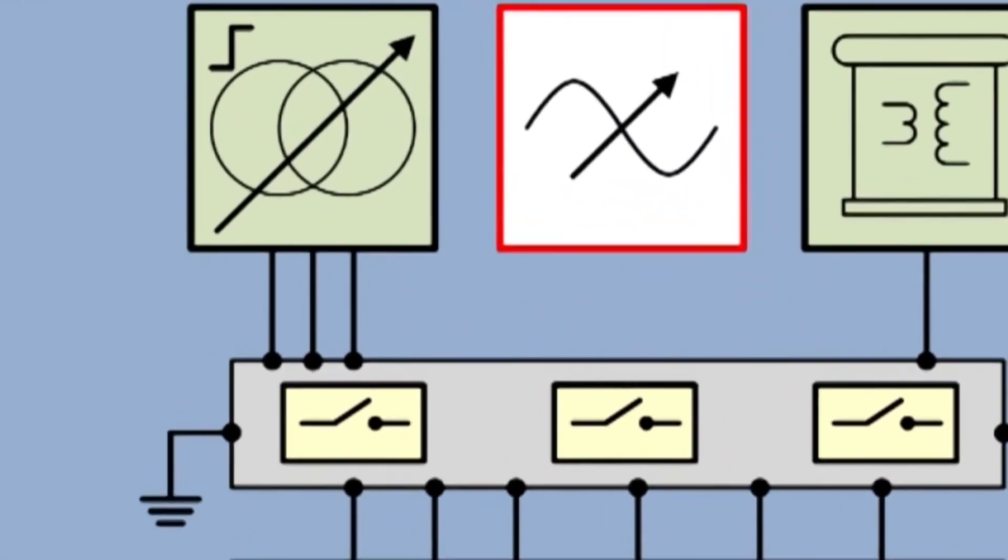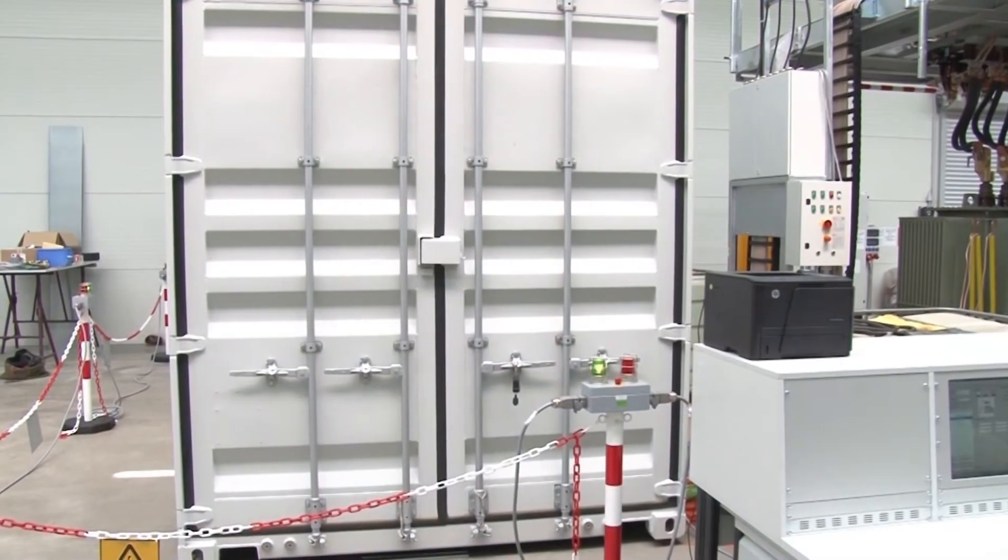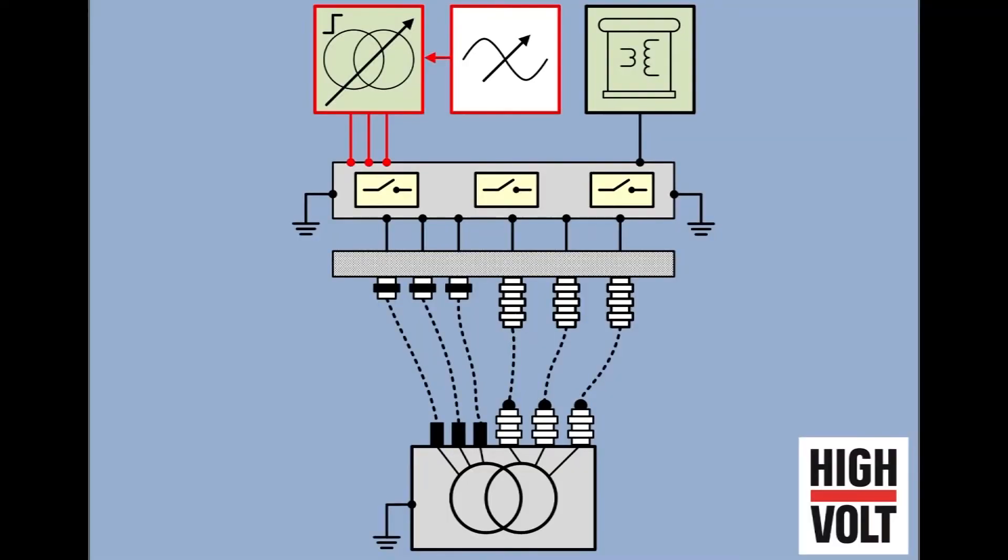Induced voltage test. The power is again supplied via the static frequency converter, but in this case with a higher frequency. The step-up transformer required for this test is integrated into the container of the converter.